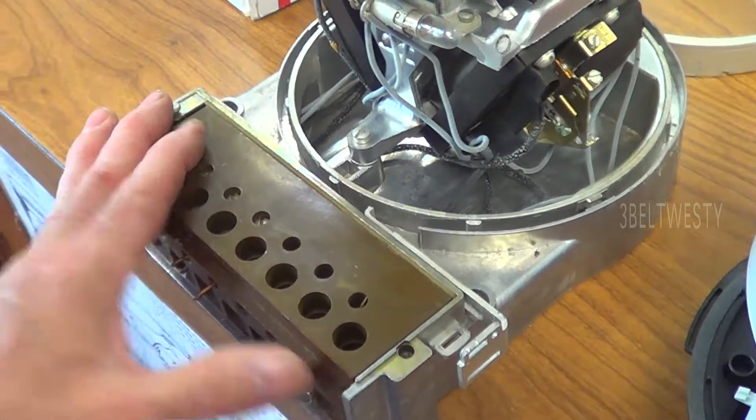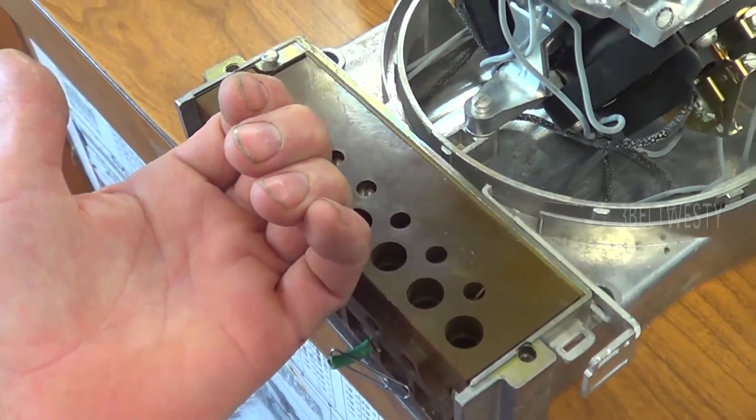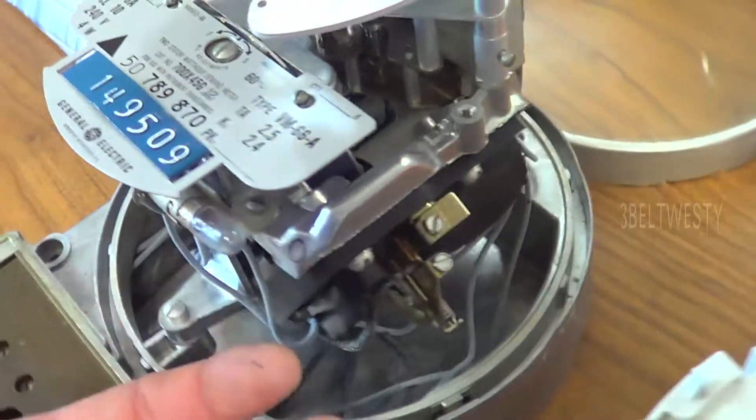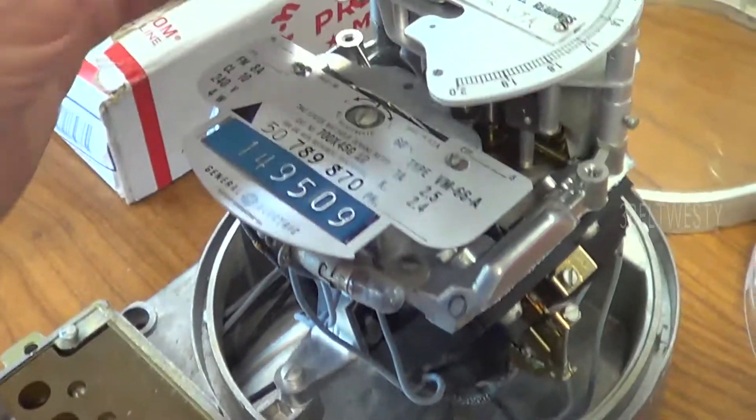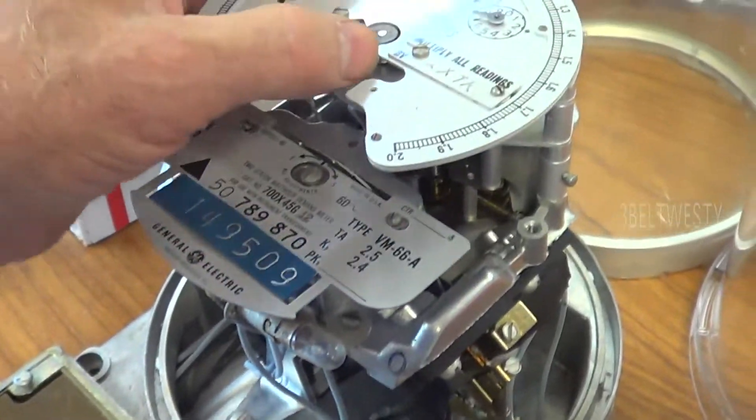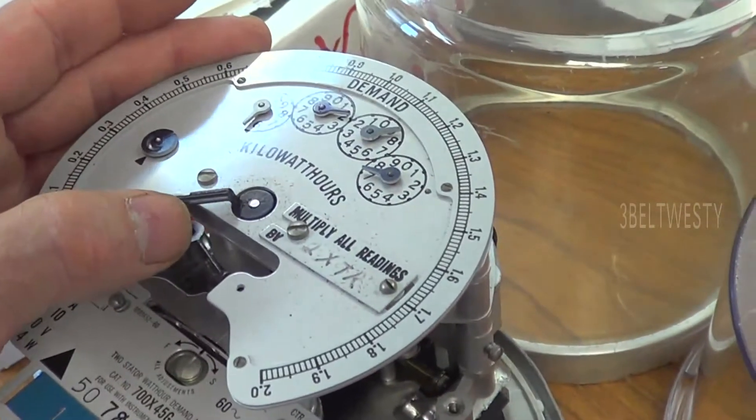The class 10 meant that this is only 10 amperes for the current portion because this is designed for current transformers. You've got a current transformer over here that generally is say 200 amps to 5 amps and then the 5 amps goes into here on each phase.